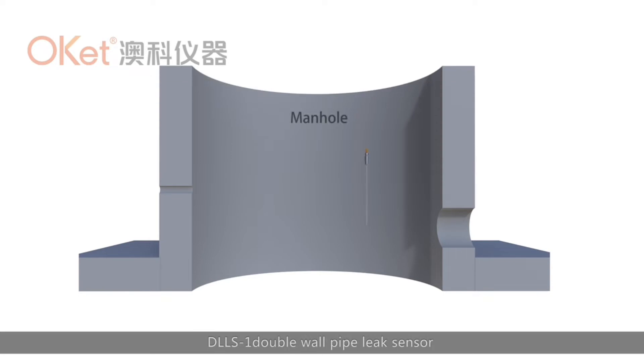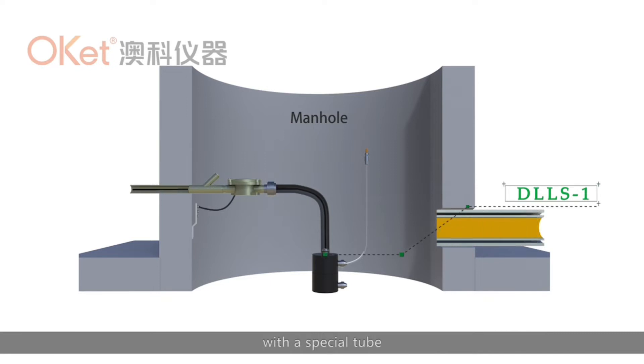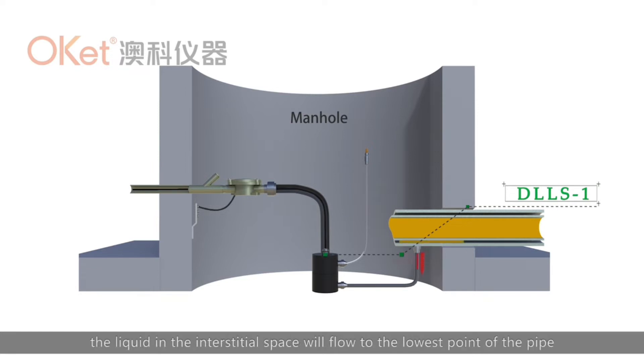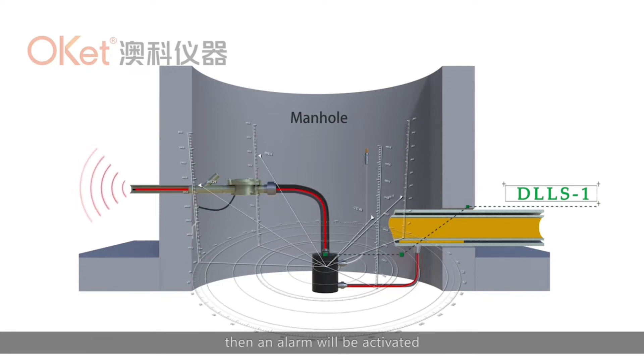The DLLS-1 double-wall pipe leak sensor will be installed at the lowest point of the interstitial space of the double-wall pipe with a special tube. If any leak happens in the pipe, the liquid in the interstitial space will flow into the lowest point of the pipe and go into the container of the leak sensor, then an alarm will be activated.